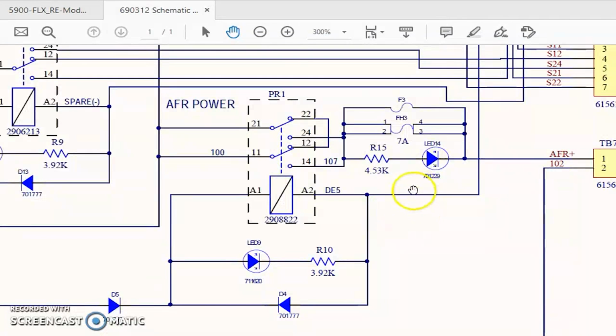Again, with the ground path not completed, I'll see voltage, the same voltage here as I do here. With the ground path completed, the voltage on this side will drop, because the resistance will drop. Think of it as a water hose. If I plug one end of the water hose, but then pressure it up, but then shut the supply pressure off, there's still pressure on that hose. But as soon as I open the discharge on that hose, the pressure escapes out immediately, and then there's no more pressure. So think of the voltage in that manner.